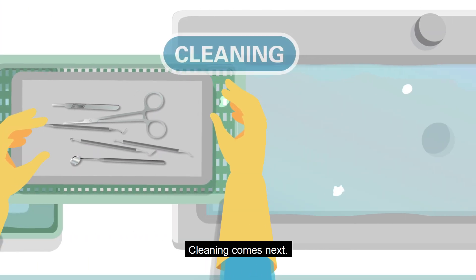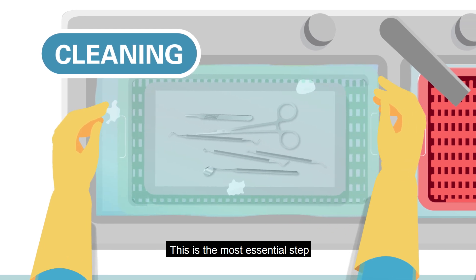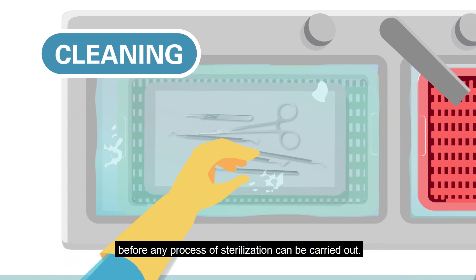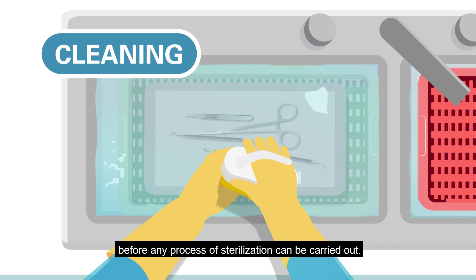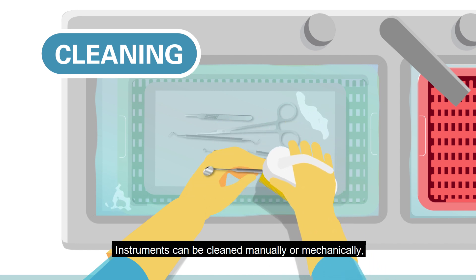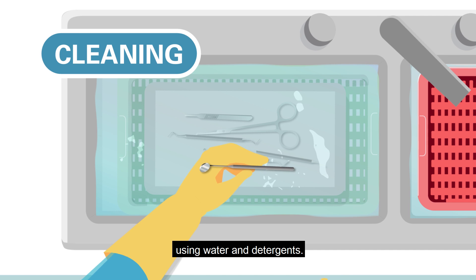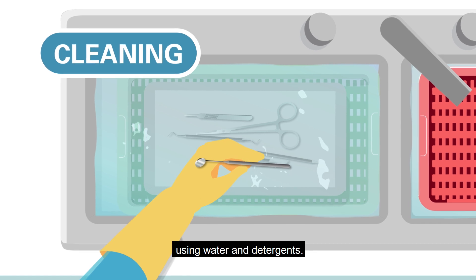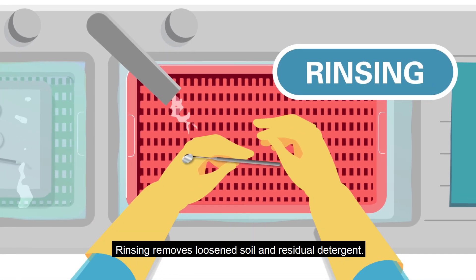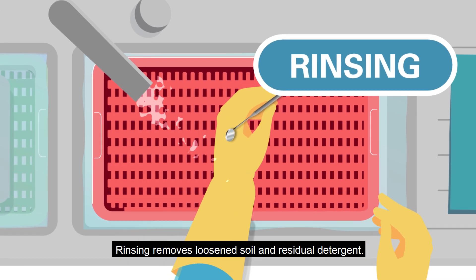Cleaning comes next. This is the most essential step before any process of sterilization can be carried out. Instruments can be cleaned manually or mechanically using water and detergents. Rinsing removes loosened soil and residual detergent.